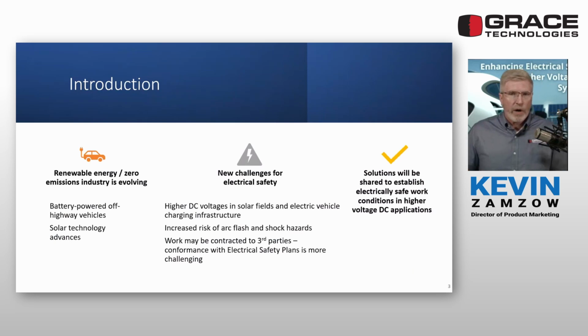We have had requests for through-door test points for absence of voltage testing for DC voltages over 1,000 volts. Initial requests were for 1,250 volts DC, but requirements have continued to grow to 1,500 volts DC for utility solar scale plant applications to over 2,000 volts DC for electric vehicles.